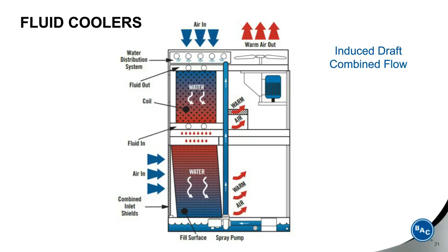However, the evaporative heat transfer occurs primarily, about 70 to 80% of it, in the fill surface, which means that the coil surface stays much cleaner and does not scale. The scaling would then occur in the fill area where it can be easily removed and through the water treatment program.